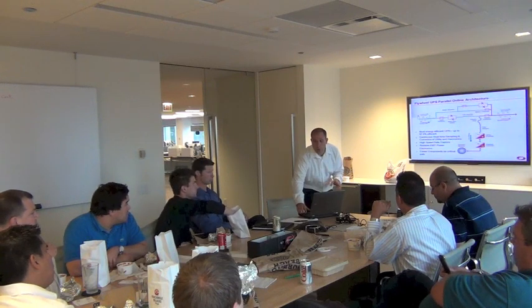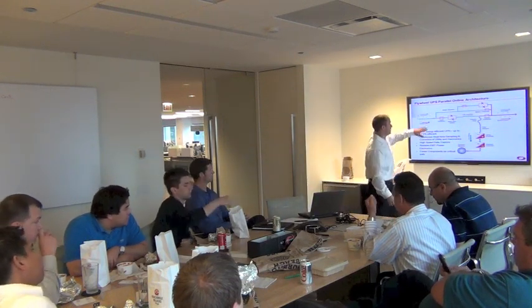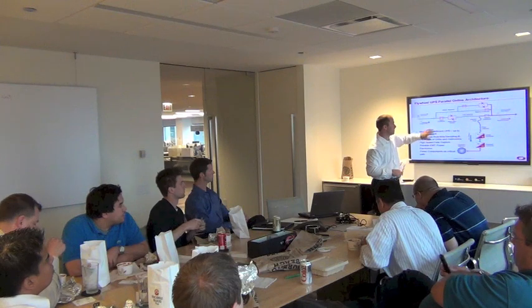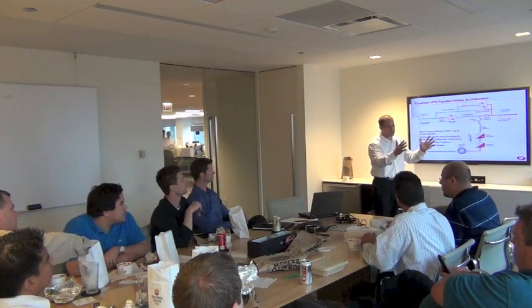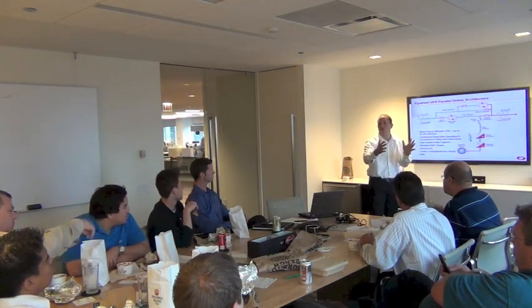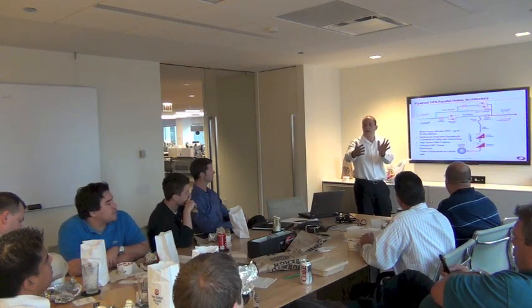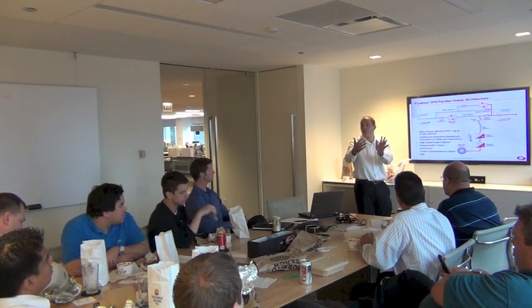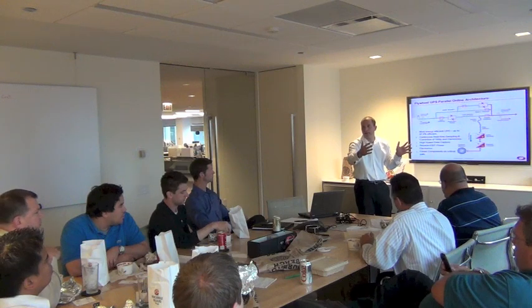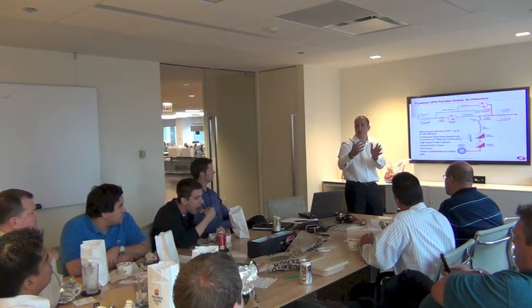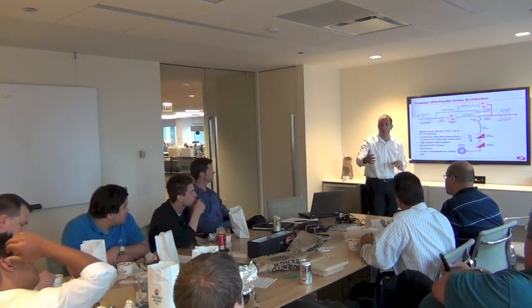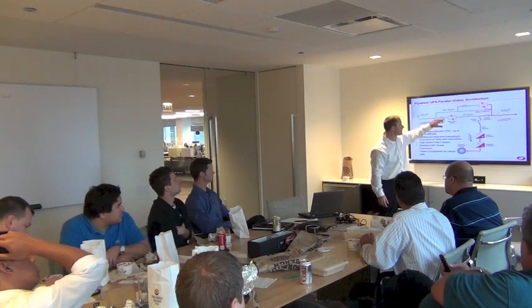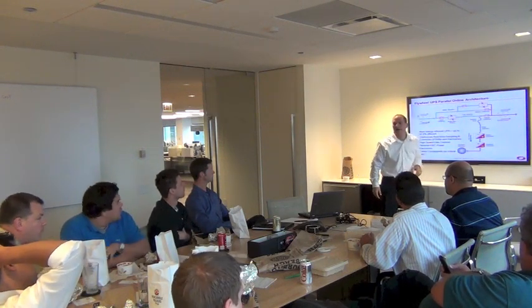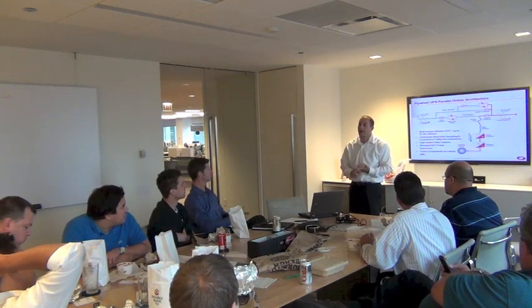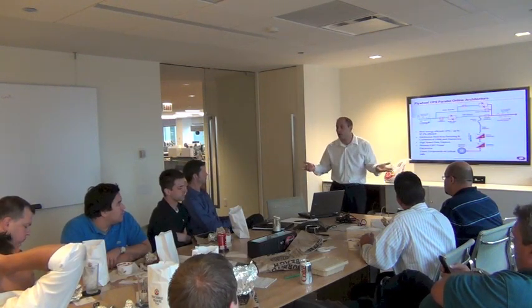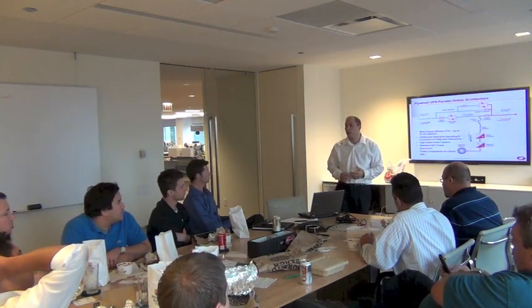No. So when we add a flywheel, that's what I was going to say, one of the bigger advantages with our equipment, and I'll show you a lineup of a multi-module system. We have an I/O cabinet and a systems cabinet that's a central frame to the UPS. What we have is referred to as a 300 expandable. So you'd start with a 300 kVA expandable system, and then you can add flywheel cabinets for redundancy or to grow in capacity. Anytime you add a flywheel cabinet, you're adding all of these critical components. You're adding a flywheel either for capacity, redundancy, or additional ride-through time.